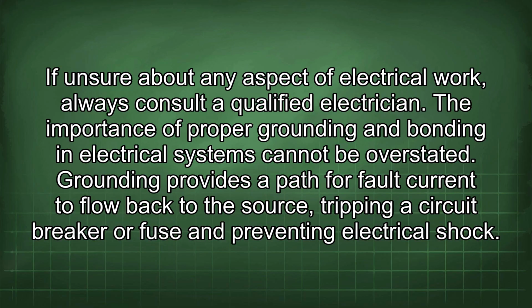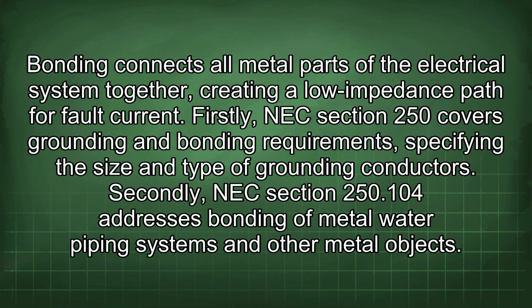The importance of proper grounding and bonding in electrical systems cannot be overstated. Grounding provides a path for fault current to flow back to the source, tripping a circuit breaker or fuse and preventing electrical shock. Bonding connects all metal parts of the electrical system together, creating a low impedance path for fault current. Firstly, NEC Section 250 covers grounding and bonding requirements, specifying the size and type of grounding conductors.